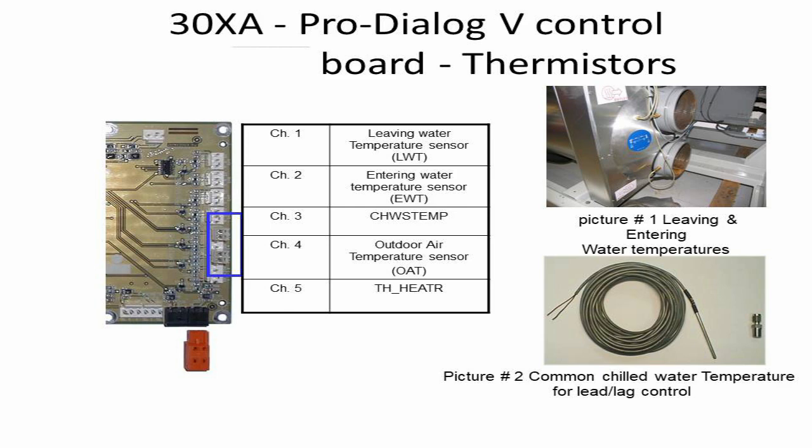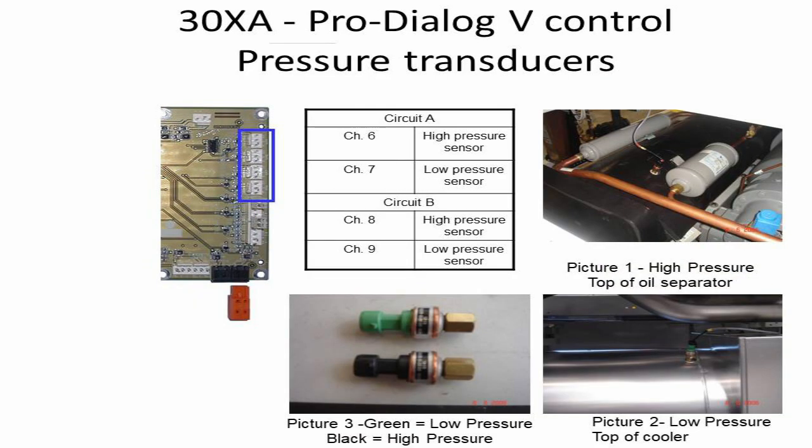The Outdoor Air Temperature Sensor is connected on Channel 4. The panel heater is connected on Channel 5. The high pressure transducer and low pressure transducer for Circuit A are connected on Channels 6 and 7.